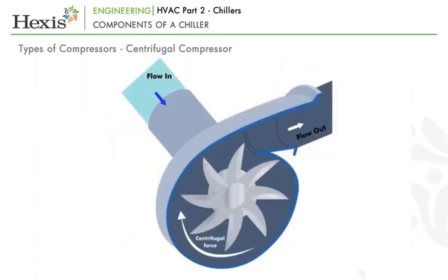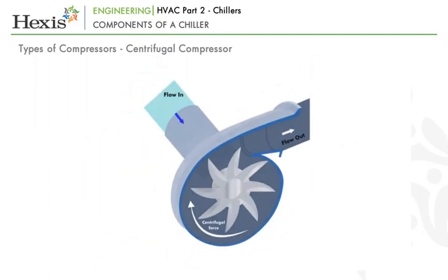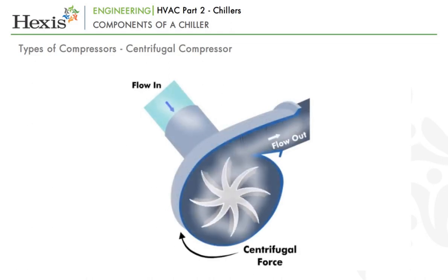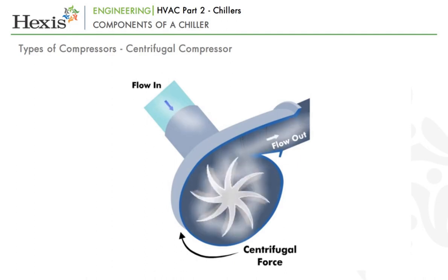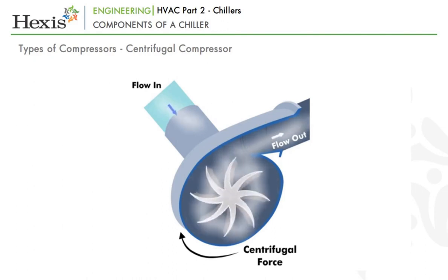The second type is the centrifugal compressor, which uses centrifugal force via a high-speed rotating impeller to increase the pressure or temperature of the gas. The gas is sucked into the rotating impeller at its axis, i.e. center, and as it moves outward it gains speed and is compressed as it reaches the outside edge of the impeller blade.